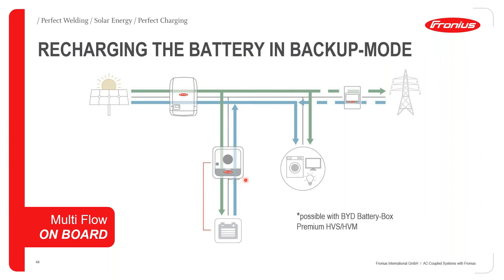What can also be done with the GEN24 inverter is that you can AC couple it to an existing Fronius Snap inverter. So in this system, I have a Fronius Snap inverter, which is AC coupled to a Fronius GEN24 Plus inverter. I have my panels attached to the Snap inverter, and the Snap inverter will then convert DC to AC to supply loads, and then you can also send excess energy to the GEN24 Plus inverter. This inverter in turn will then charge the batteries, and it can also discharge the batteries in order to supply the loads as well.